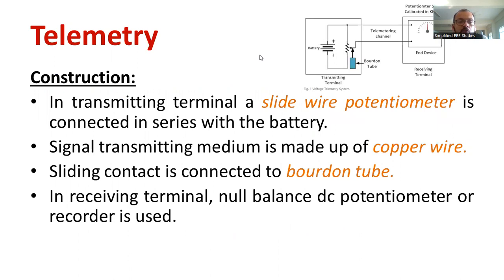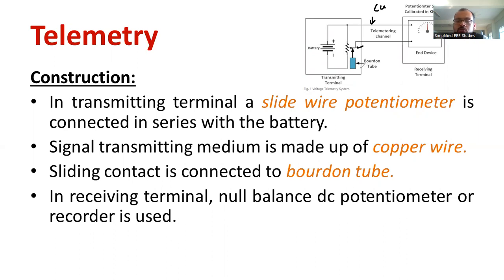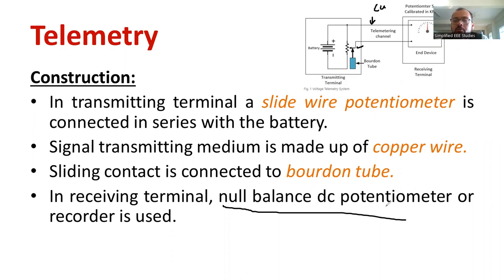The major construction component is a slide wire — the slide wire I already showed you. The signal transmitting media is copper wire. The sliding contact is connected with the Bourdon tube because, with respect to changes in the physical system, the Bourdon tube gets activated. As the pressure changes, the Bourdon tube also changes. At the receiving end side, there is a null-balanced DC potentiometer which is calibrated in terms of pressure — kilo Newton per meter square. A recorder can also be used.